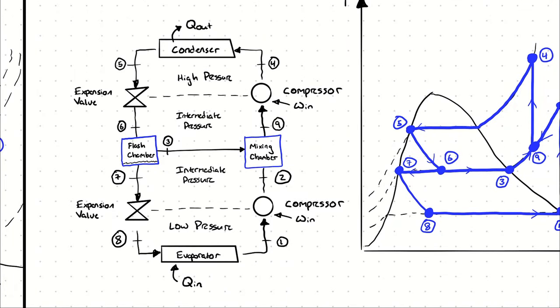In this cycle, we have a high pressure at which our condenser operates. Then we expand to an intermediate pressure where the stream is split. Some of it — the vapor — goes into the mixing chamber. The rest — the liquid — goes down into a low pressure refrigeration cycle. On the low pressure side, we have a low pressure at which our evaporator operates, and then two compressors: one taking it from low pressure to intermediate pressure, and one from intermediate pressure to high pressure. Note that these nine state points have different mass flow rates. There is one mass flow rate at 9, 4, 5, and 6. There is some mass flow rate at 7, 8, 1, and 2. And the mass flow rates at 2 and 3 must sum together to equal 9.